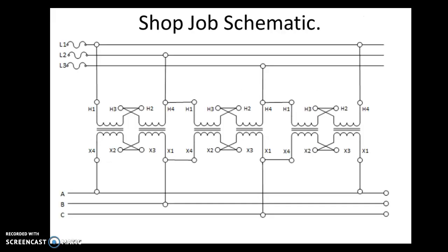So this would be the schematic for the shop job. Here you should notice that power is being brought in on the top side, line 1, line 2, line 3. And power is being brought into the beginning of each transformer, but also the end. So if we were on the first transformer with line 1 connected to H1 and line 2 essentially connected to H4, the rating of this transformer is 120/240 as noted on the shop job. It is a 1-to-1 ratio, so that means that 208 will split here and we will see 104 volts measured between H1 and H2 and 104 volts measured between H3 and H4. So that gives us the full 208.